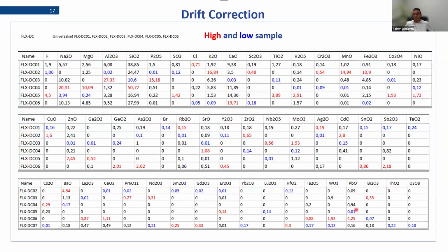drift corrected. Important is always that you use your application settings to measure them, that you have then exactly the same conditions. They are also designed in a way that if you look only on one sample, there are as few line overlaps as possible between neighbor elements, so that you always have freestanding peaks to get the best precision possible without any line overlaps.